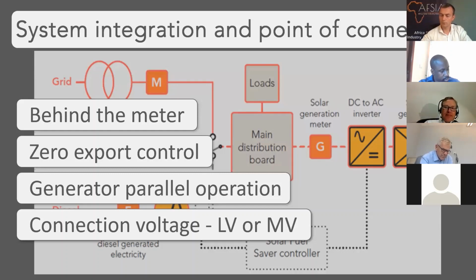This meant that, or this means that the solar system will likely need a step-up transformer to step it up from the low voltage 415, which is your average three-phase commercial voltage, up to 11 kV, which is more your distribution voltage. For Mombasa Airport, we used an underground cable to then take the power from the solar site back to the connection point, and with the inclusion of all the correct medium voltage switchgear, of course.